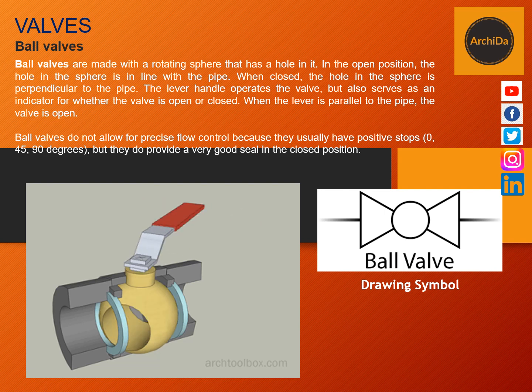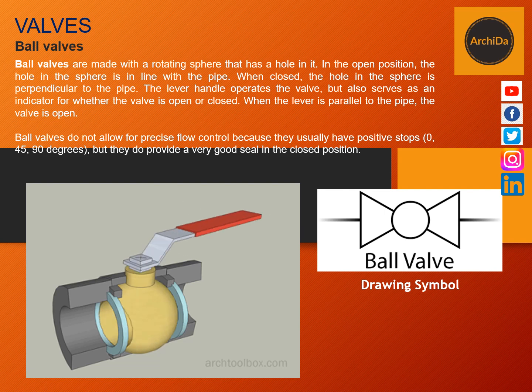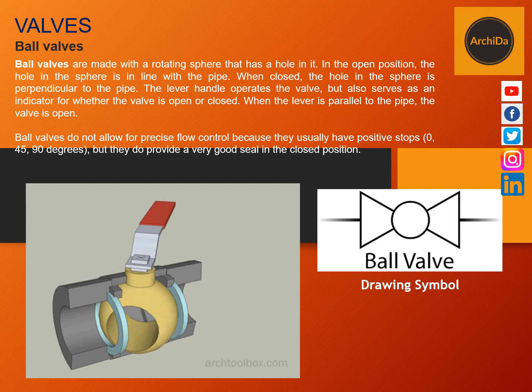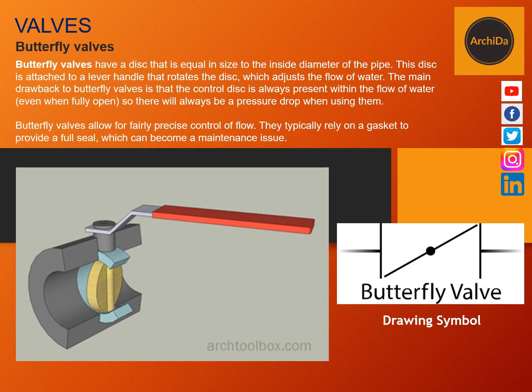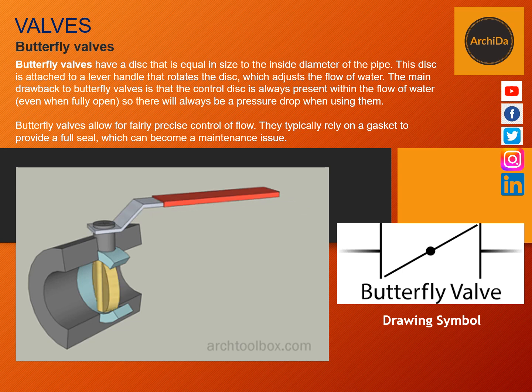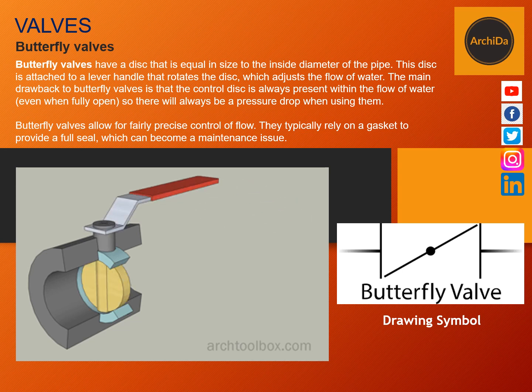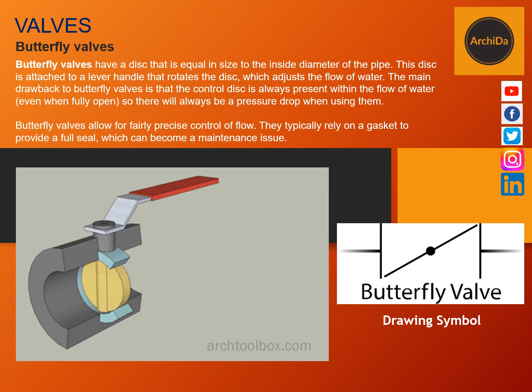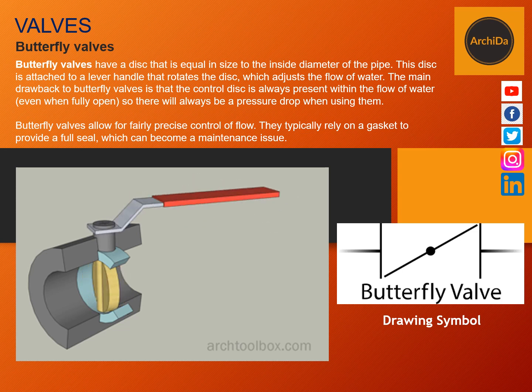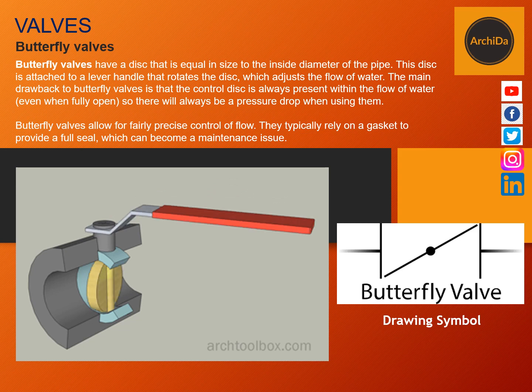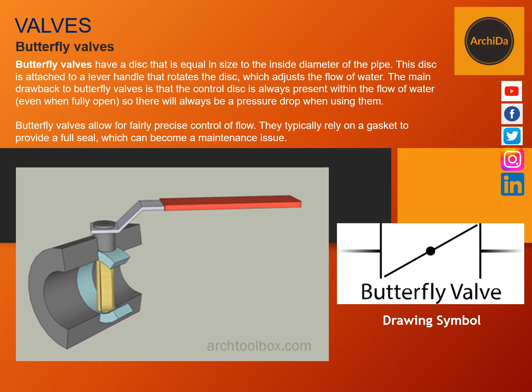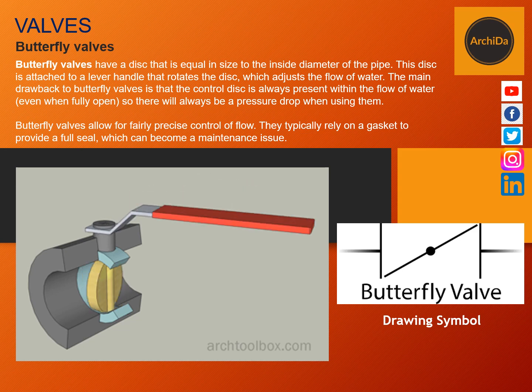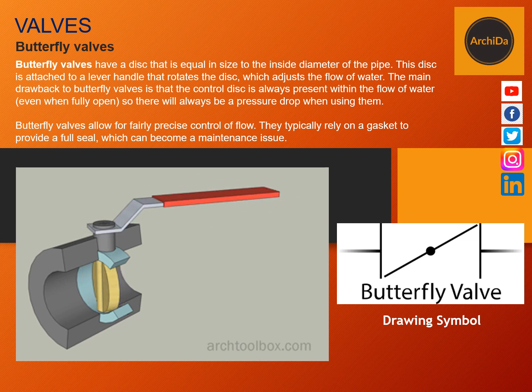The lever handle operates the ball valve and also serves as an indicator of whether the valve is open or closed. Similar to a ball valve, we have what is called a butterfly valve. A butterfly valve has a disc that is equal in size to the inside diameter of the pipe. This disc is attached to a lever handle that rotates the disc, which adjusts the flow of water. The main drawback to butterfly valves is that the control disc is always present within the flow of water even when fully open, so there will always be a pressure drop when using them.